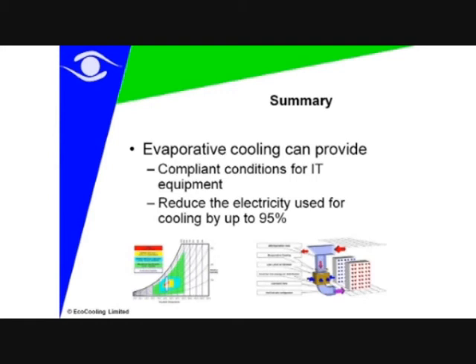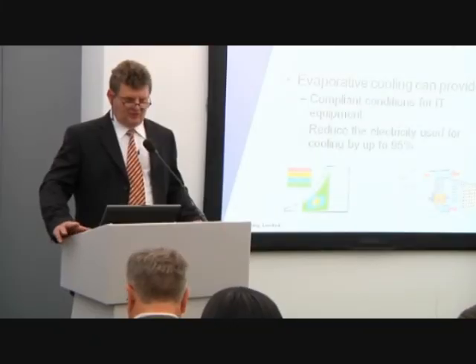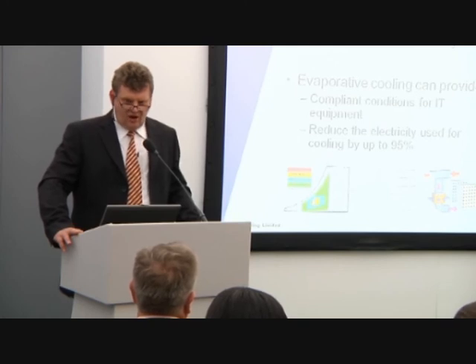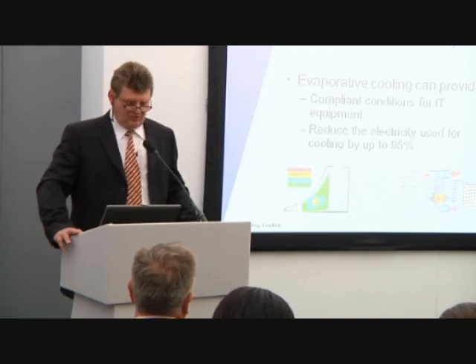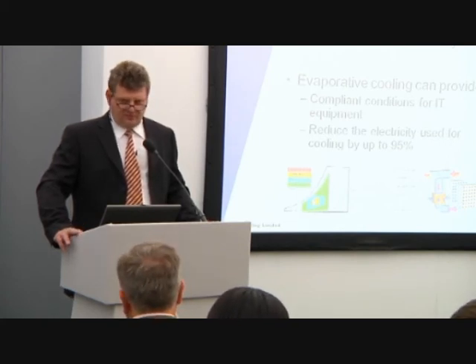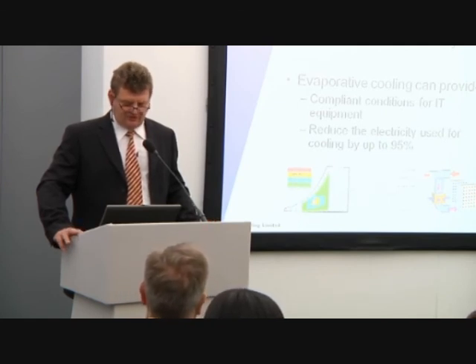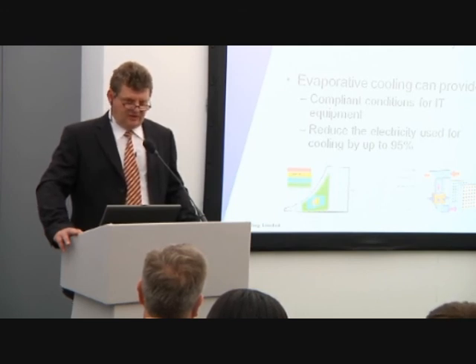Using fresh air systems and evaporative cooling, we can create compliant conditions for modern IT equipment. Modern IT equipment is robust — it has a wide operating temperature range and a wide operating humidity range. It doesn't require perfectly sterile, perfectly dust-free conditions; we don't have open drives or open bearings now. If you embrace that widening of operating standards, you can implement a ventilation scheme based on these principles and reduce your cooling energy bill by over 90%. In most cases, that means you can reduce the total energy usage of your data centre by half, with a capital investment that could pay for itself in under a year.